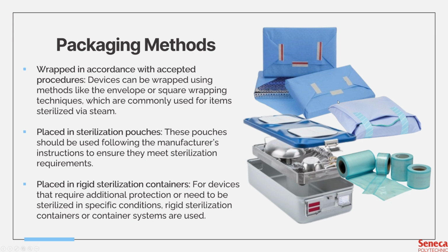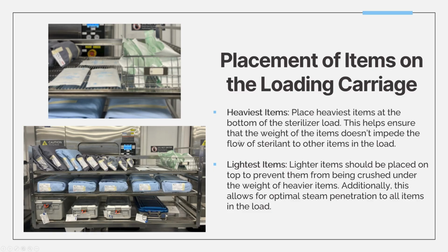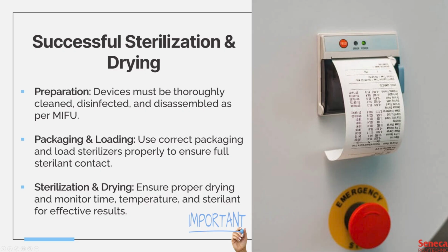But for some sterilization methods such as liquid chemical sterilization like hydrogen peroxide gas plasma, you cannot use reusable wrappers because these reusable wrappers will absorb all of that chemical sterilant. This one, they are thin enough where the chemicals could actually penetrate through and successfully sterilize instruments. Right. All right.